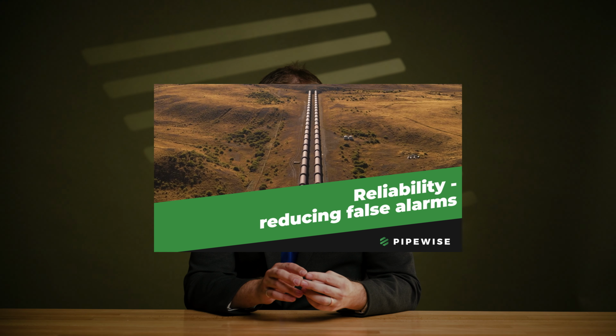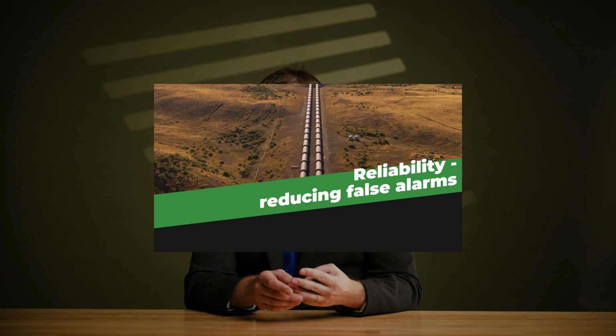those sorts of events. The third one that I would talk about is going to be reliability, and that ties into the false alarm rate. So how frequently is the system alarming compared to what your actual leak rate is in a given month? How frequently are your operators going to be dealing with those false alarms? Because that can definitely create additional workload for them with having to manage that, or eventually, worst case scenario, it just turns into operator fatigue where they start to ignore that entirely.